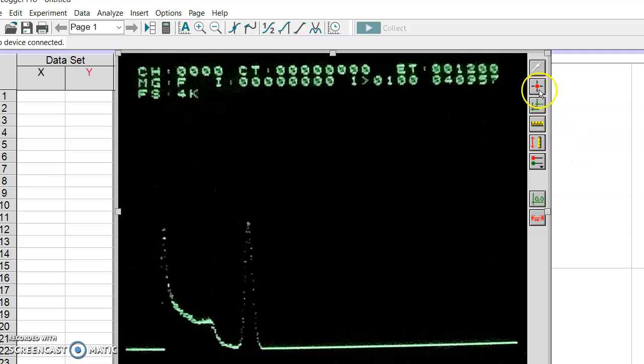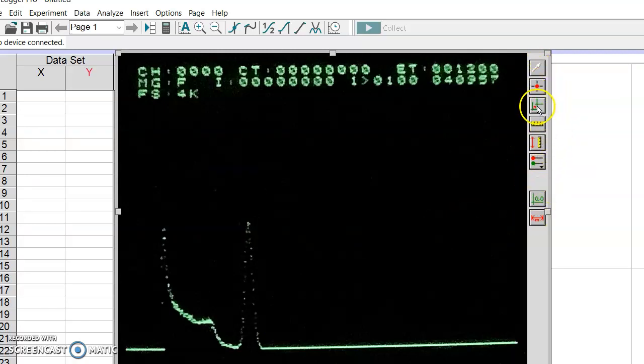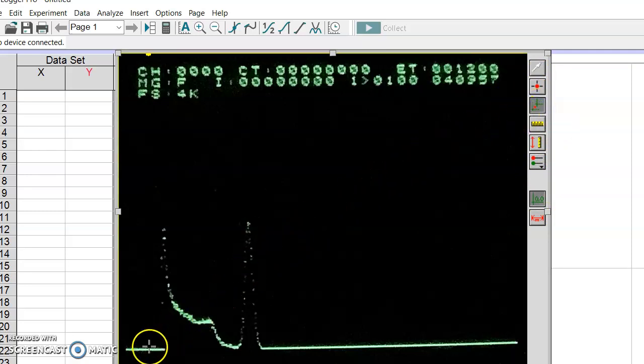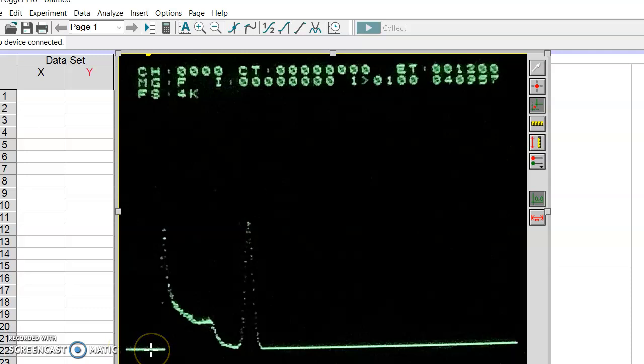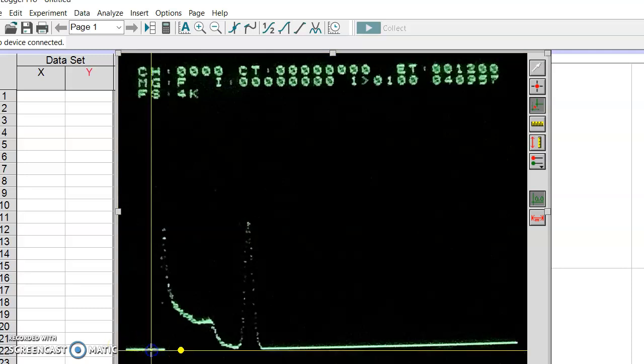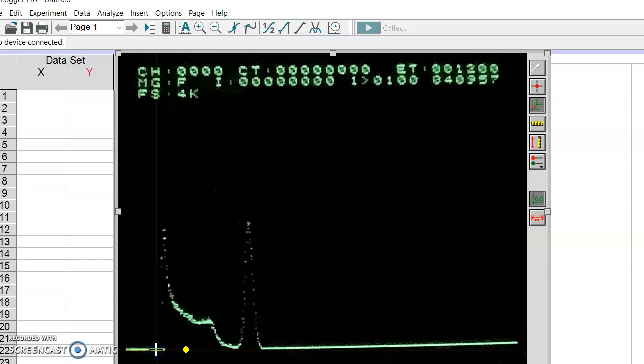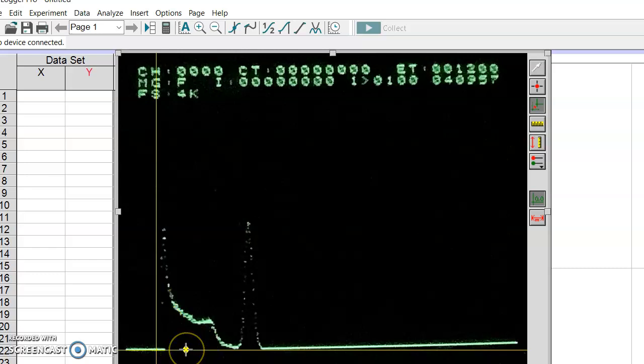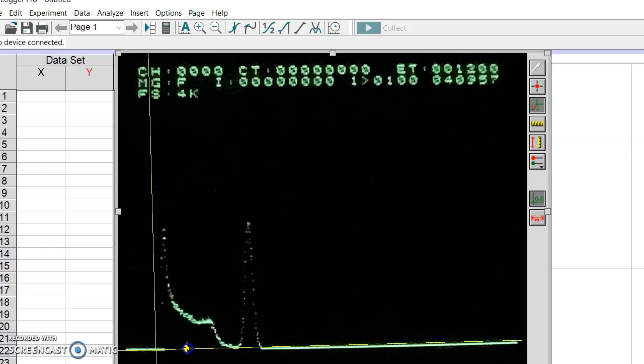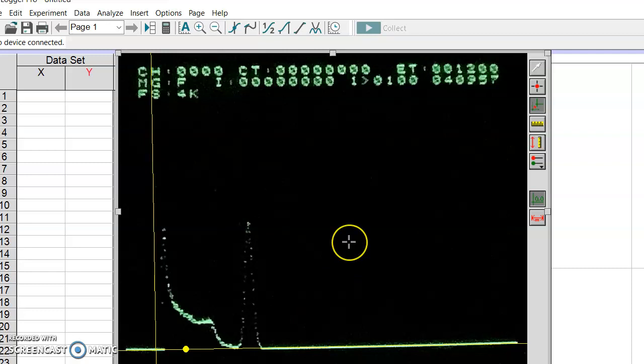There are three steps. The first step is to set the origin. On the right side of this graph you see a few buttons. If you click the third one, Set Origin, and you move your mouse to the blue line, you want to put the origin where the zero intersection will be, where the first detection happens. You see the yellow dot, you can click the yellow dot, you can rotate the x-axis so that it matches with the blue line. Step one is done.